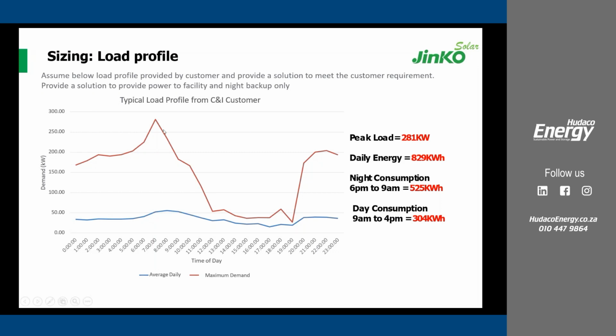So you can see how this load profile looks, and what you can also see is that the peak load demand usually occurs during the day, in the morning hours. It looks like a large load with more demand. Maybe the heaters are working in the morning and also at night, after 8 p.m. The rest of the hours the load is quite low. What we're looking at is the average load and also the maximum demand, which will actually dictate the sizing of our PCS.